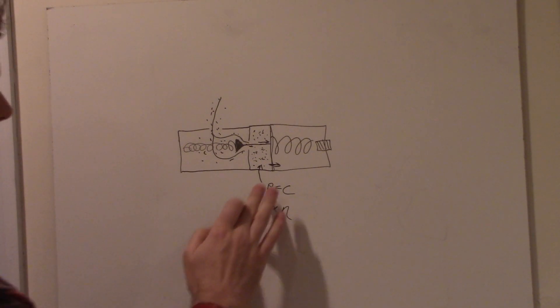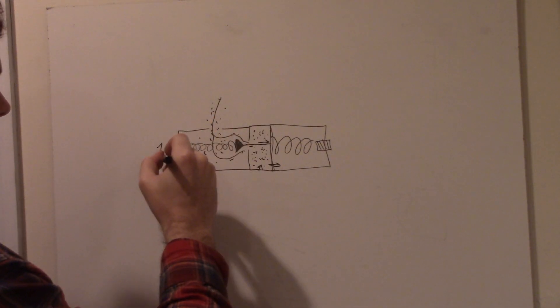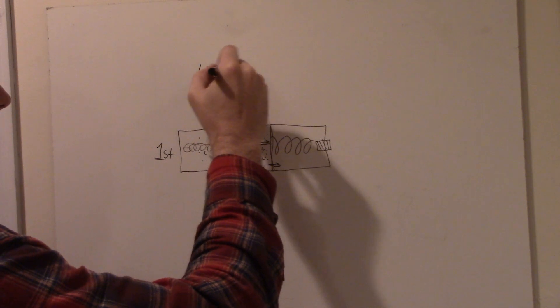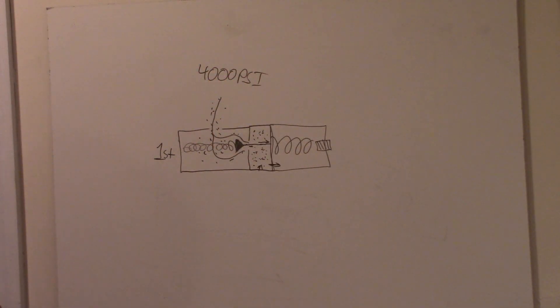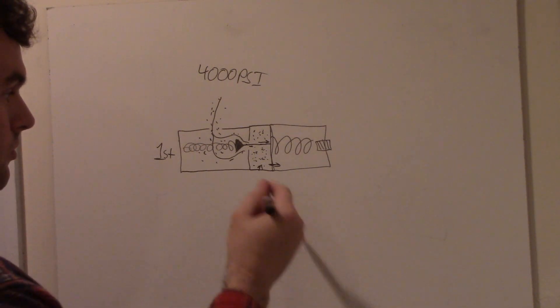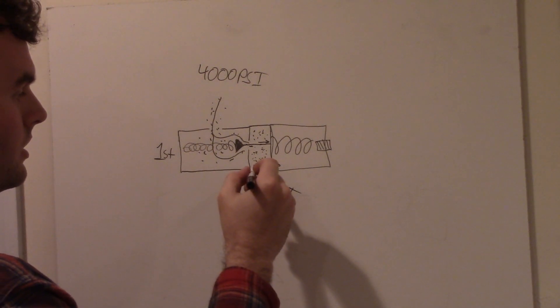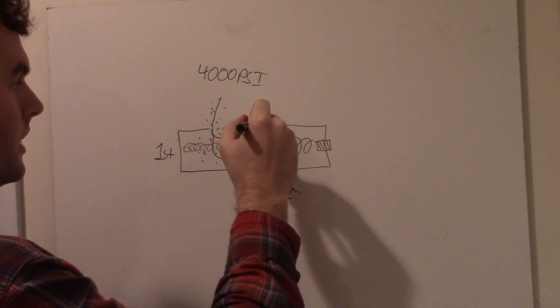Now, the speed of these molecules is only dependent on the temperature. With the gas, the speed really doesn't depend on the pressure, but the pressure depends on the speed of the molecules, the temperature, and the number of them. So in essence, this regulator is just trying to keep the number of gas molecules in this holding cell relatively constant. This is a two-stage regulator, so the first stage is going to go from 4,000 psi down to some intermediate value, maybe 500 or something.